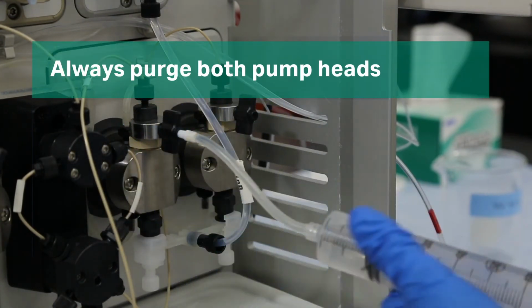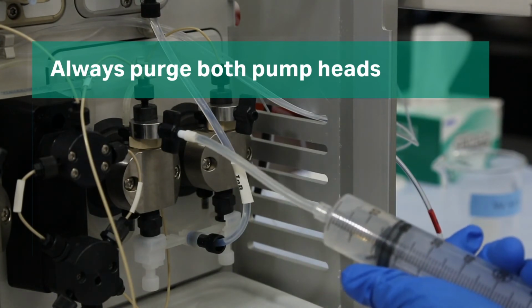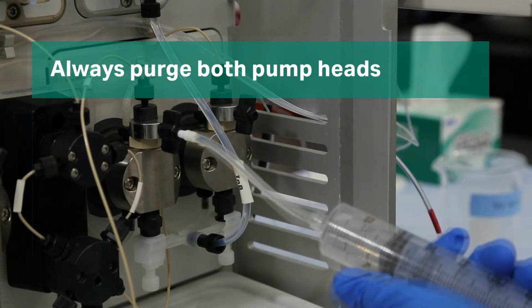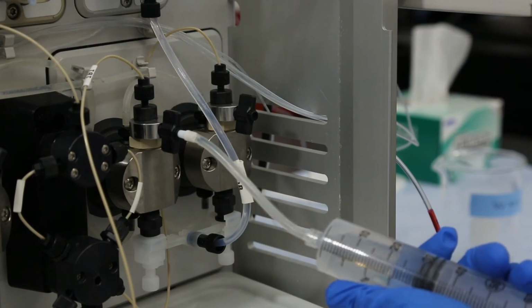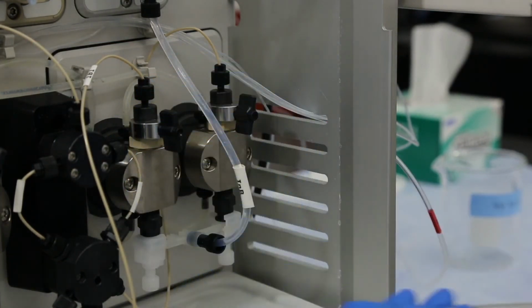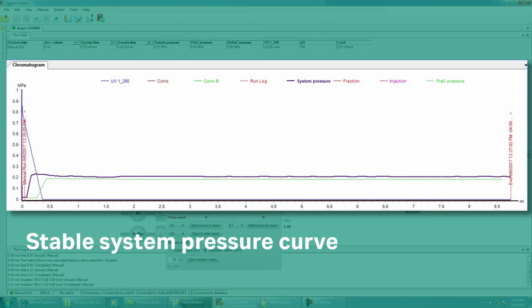It is very important that you always purge both pump heads when priming the pump. When you are finished, ensure both purge valves are tightly closed. Set a flow rate and check the flow coming from the waste line to see that it is even and consistent. The pressure curve should also be stable.